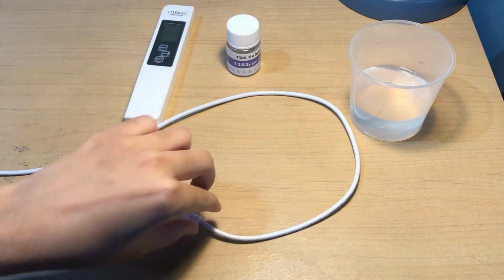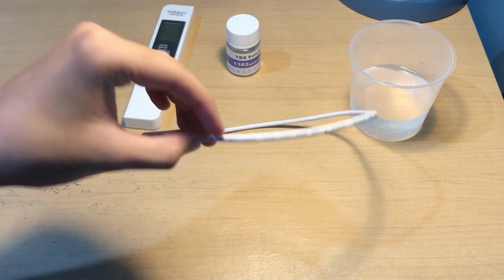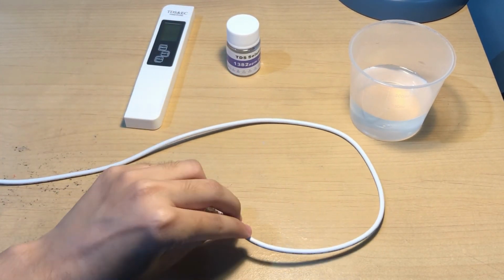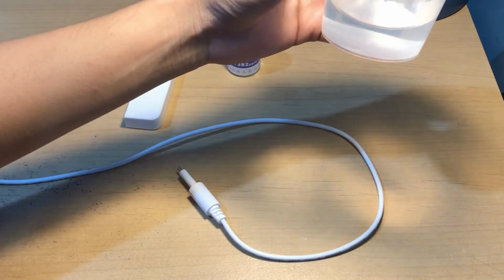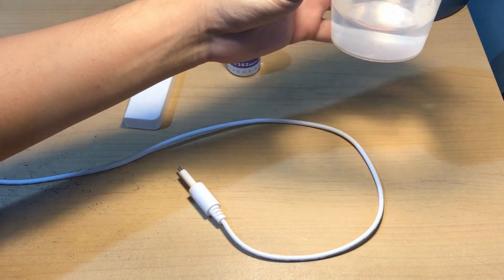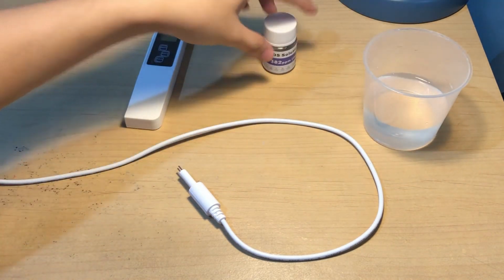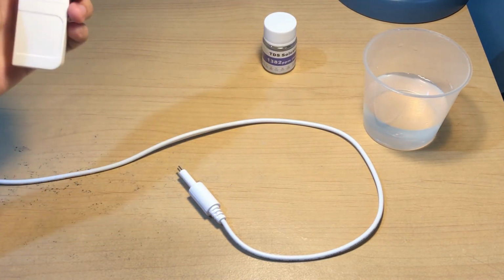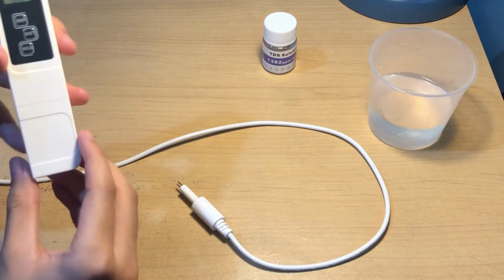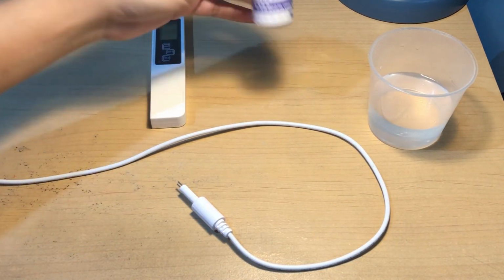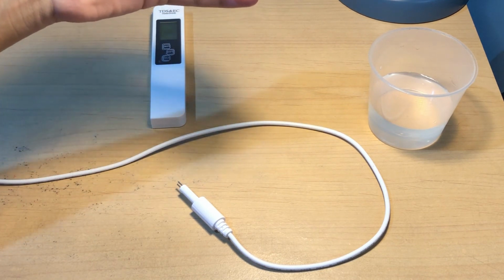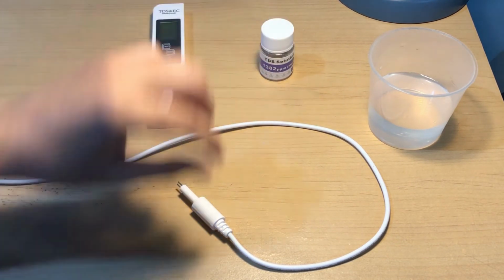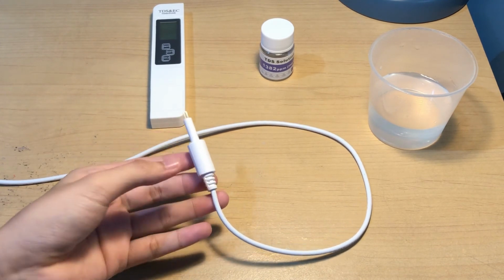Before the data analysis of the calibration process for the TDS sensor, I will demonstrate the calibration process for the TDS sensor. So now we are going to calibrate this TDS sensor from Keyestudio that we are going to use in the system. To calibrate this TDS sensor, I'm going to submerge the sensor probe into the solution. In the solution I've already added a pinch of salt so that it has some ppm value in it. I am using this TDS meter or TDS pen to verify the solution ppm value. This TDS meter has already been calibrated using this TDS solution. The reason why I didn't use this TDS solution is because the ppm reading exceeds the measurement range for this Keyestudio TDS sensor to be used in the system.